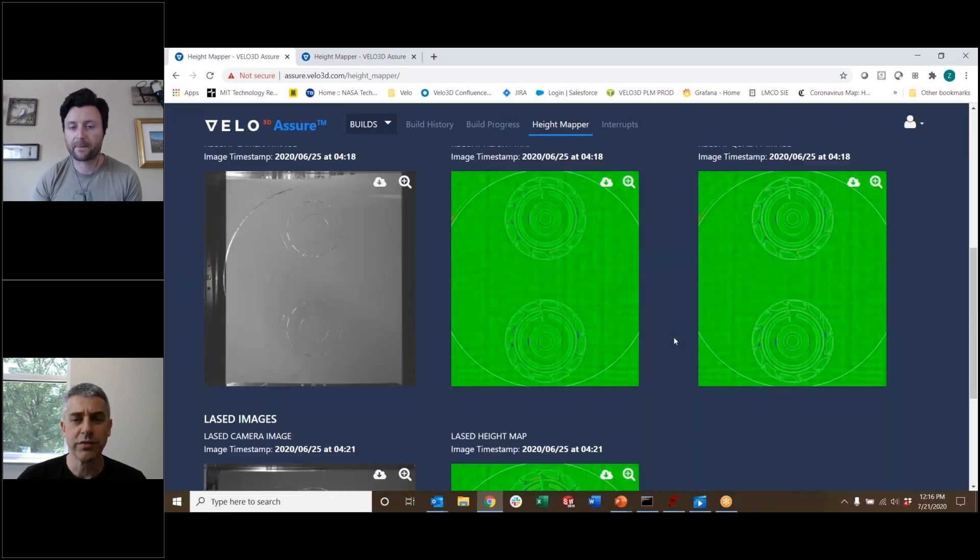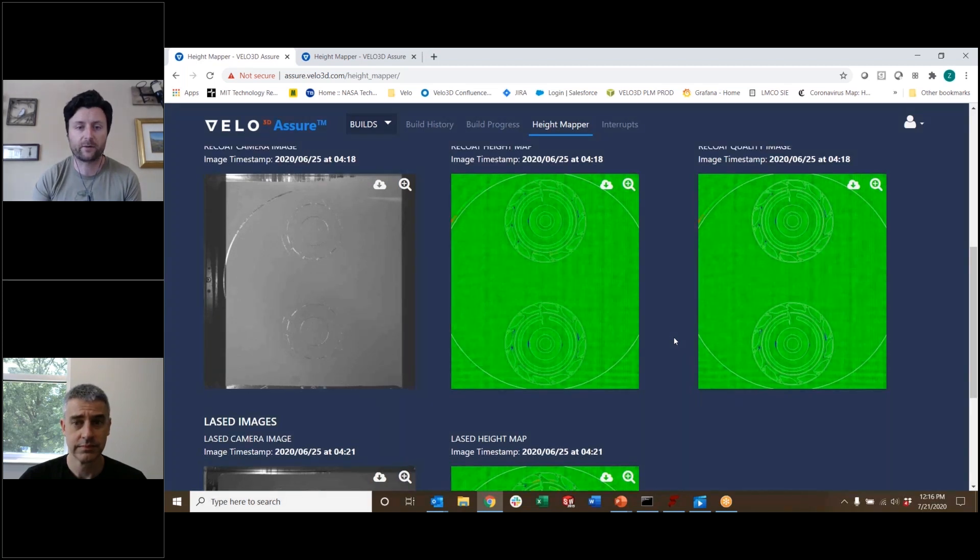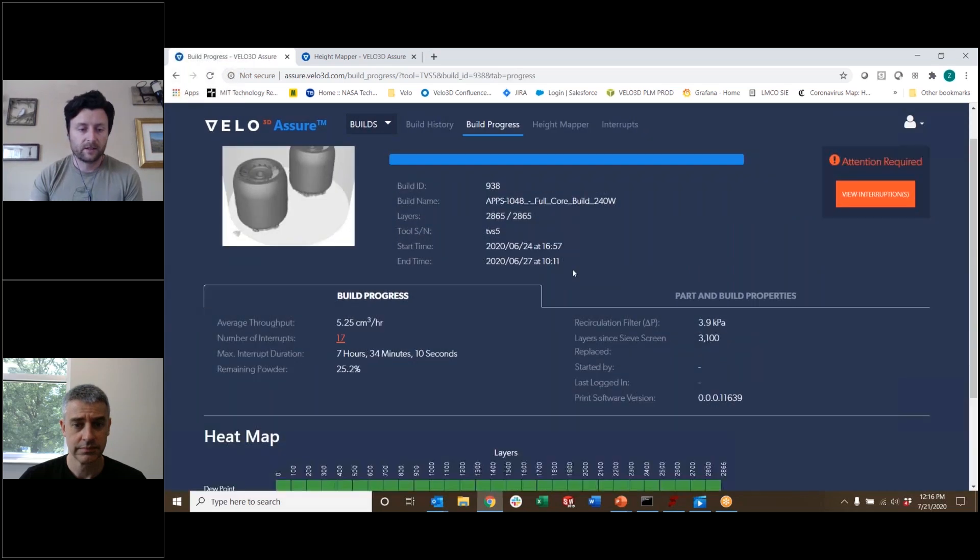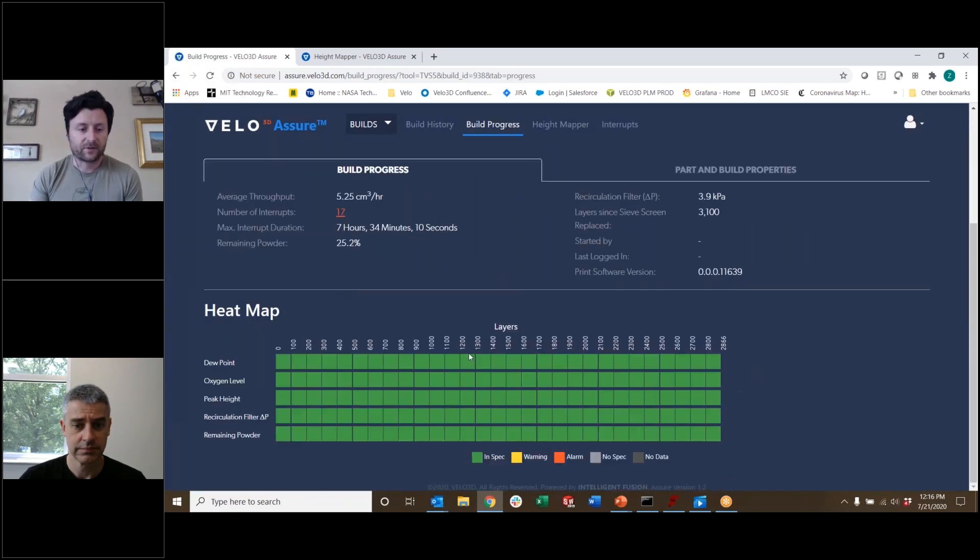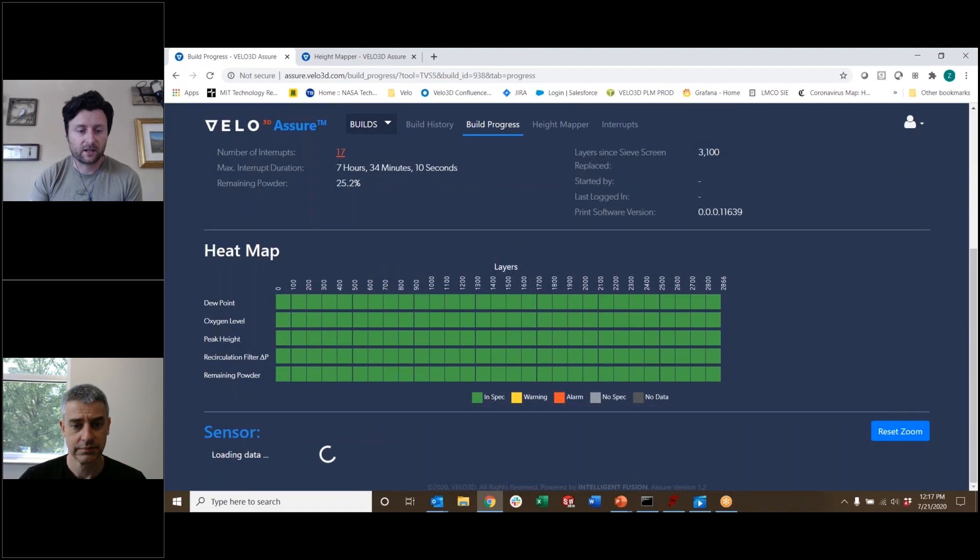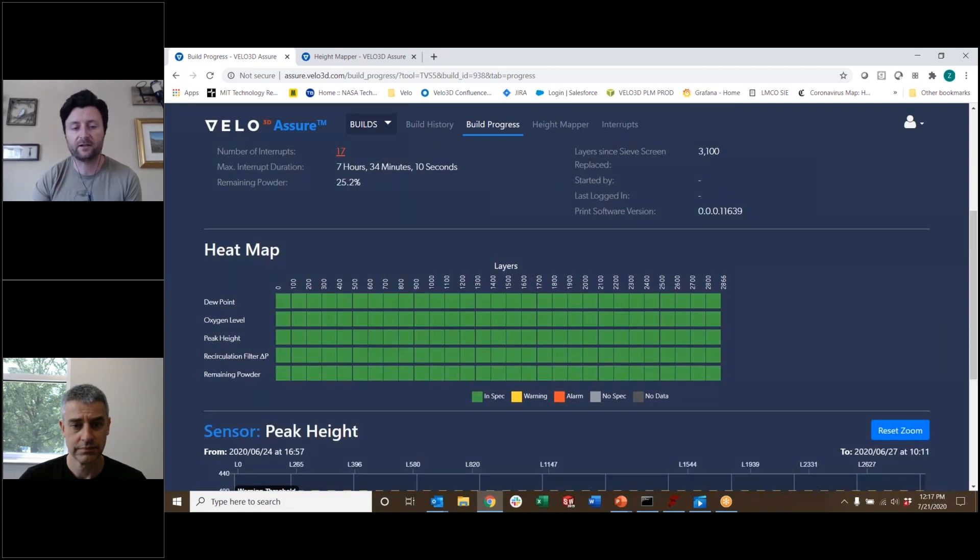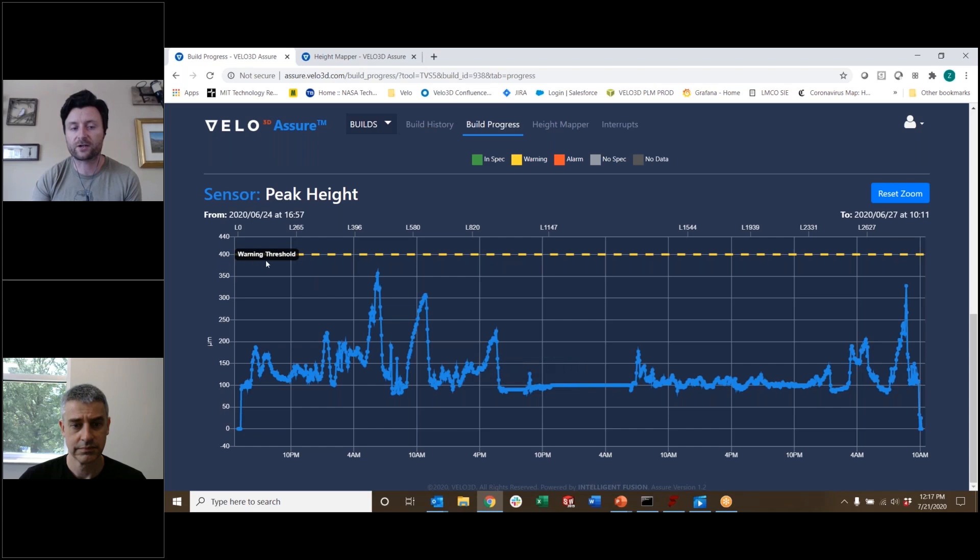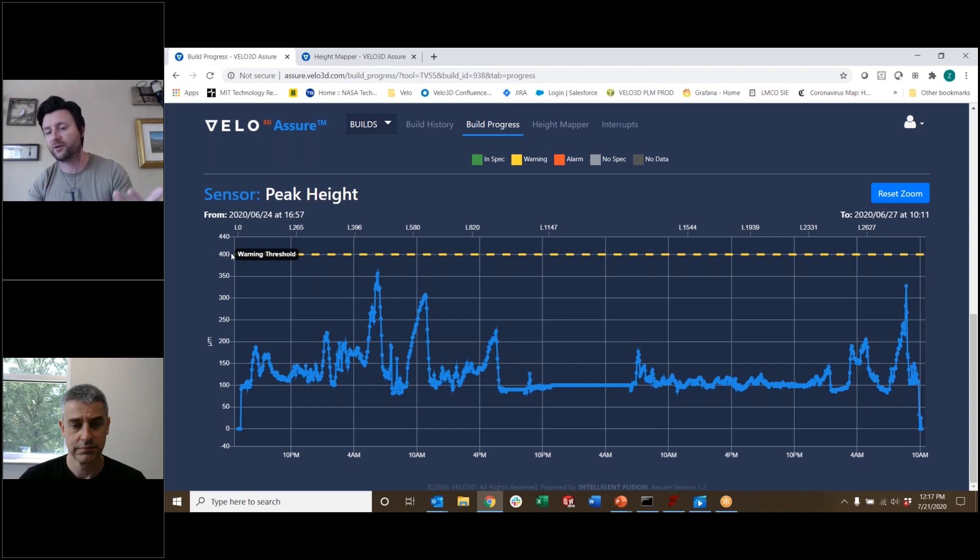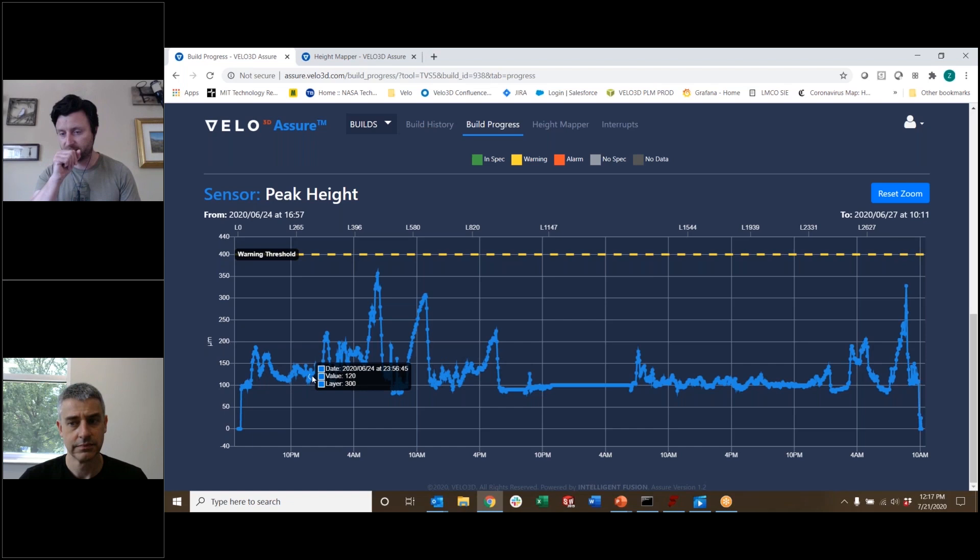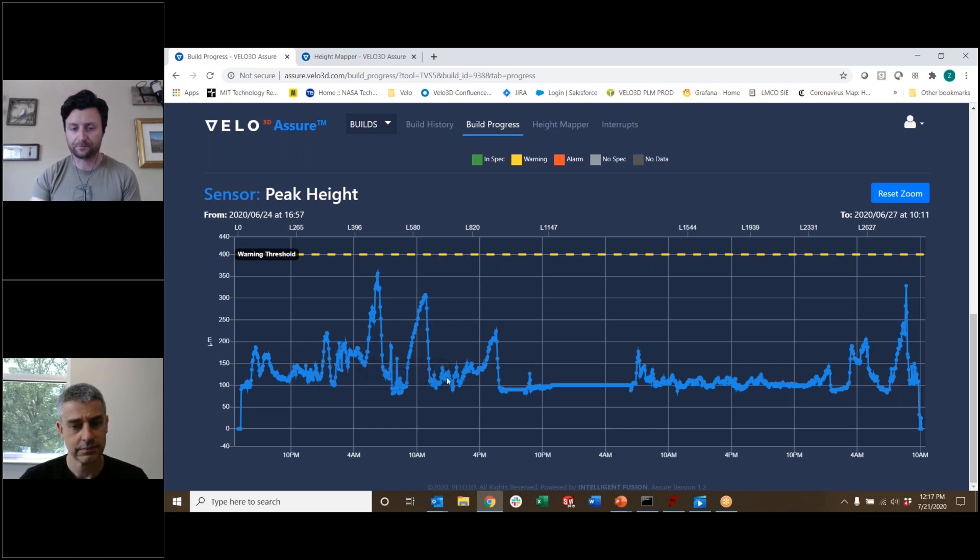Is the system watching for that and responding to too much red? Yes. Yeah, absolutely. And so I think if I went back, let me see if I can do that. So on this heat map, when we look at the peak height, it's going to load all the data for every layer. And what this is showing is the peak height for every single layer. So you have a data point on every layer. And the warning threshold is set here to be 400 microns. So that's saying if something protrudes more than 400 microns, that's a problem. But you can see for this build in particular, we didn't get to that warning threshold and everything seems to be relatively well behaved.